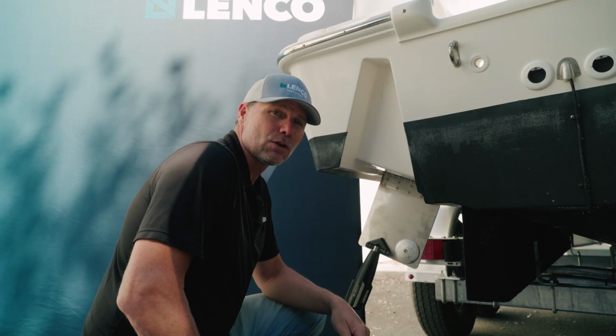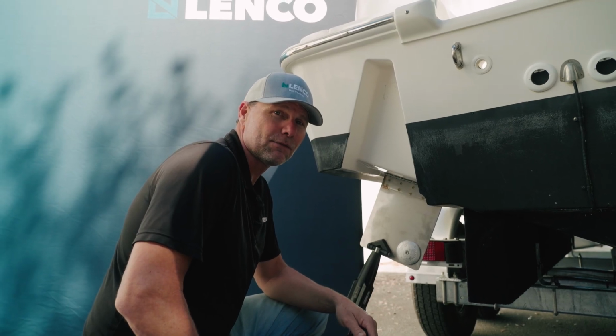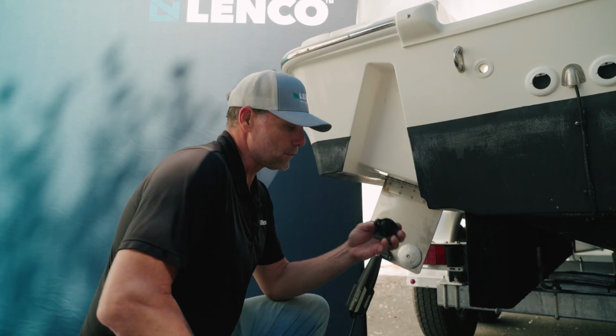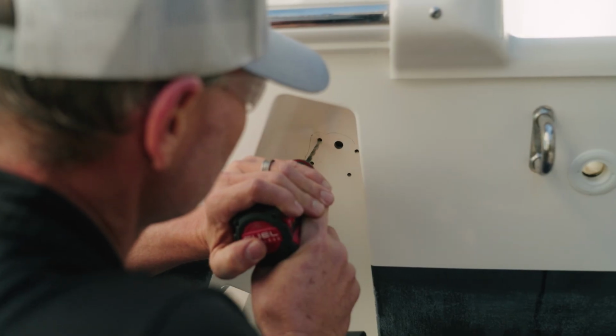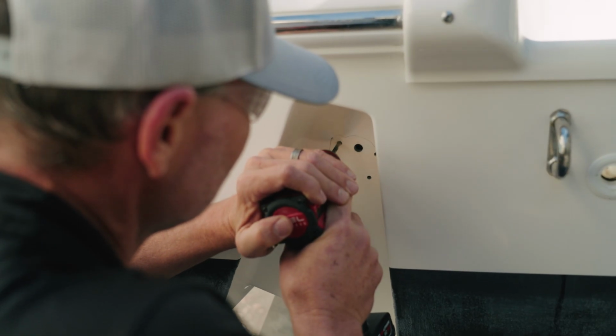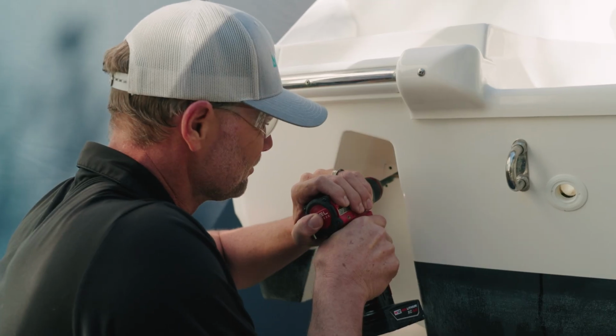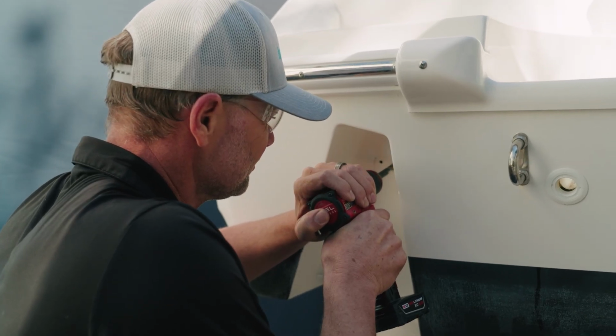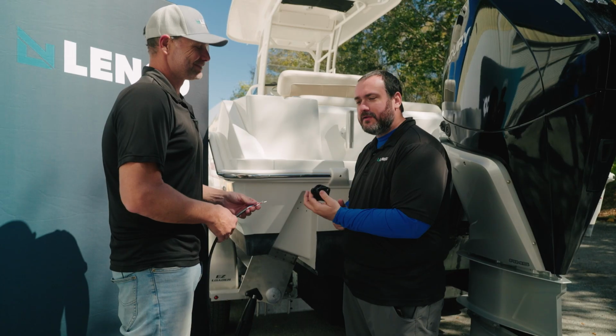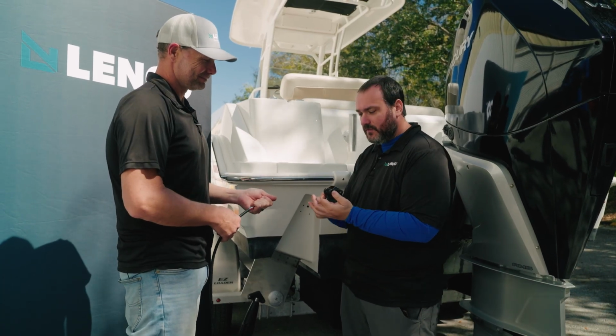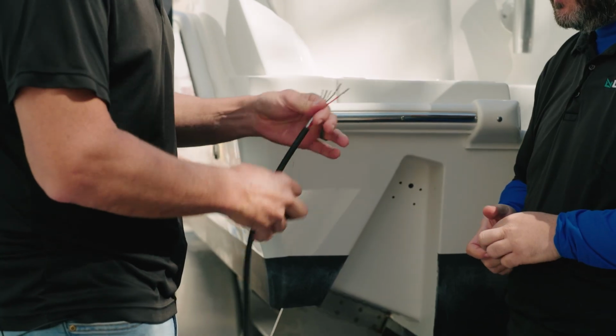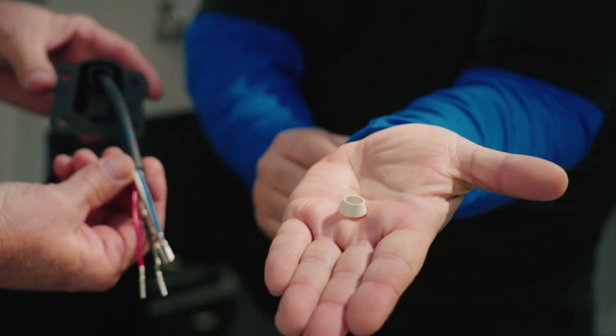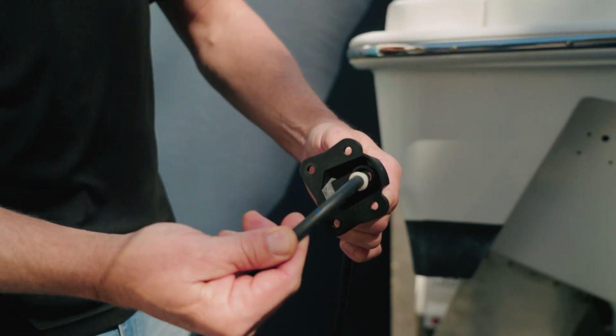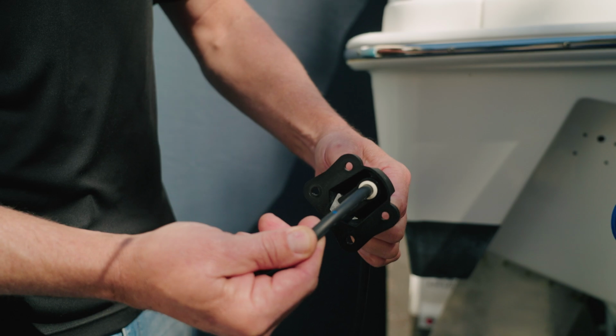Okay, so now that we have our holes mapped out and where they need to be for the upper bracket, we're going to go ahead and drill the 4 holes on the bracket itself where the mounting screws go with a 3/16 drill bit. For the center hole where the cable passes through, we're going to use a 7/16. Okay, now we're going to install the upper bracket in the system. So first we're going to pass the wire through the front of the upper bracket. And then we have our gland seal. This will then get installed on the wire with the tapered end, the smaller tapered end, resting in the bracket.